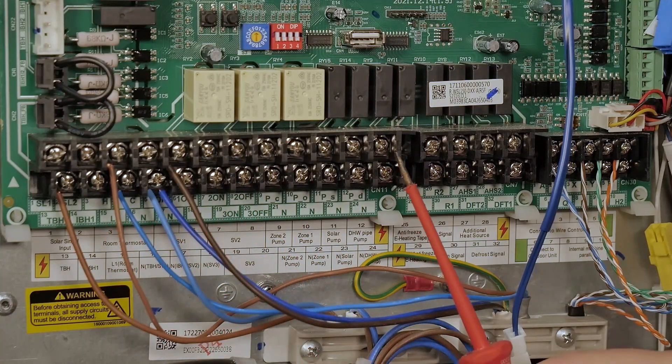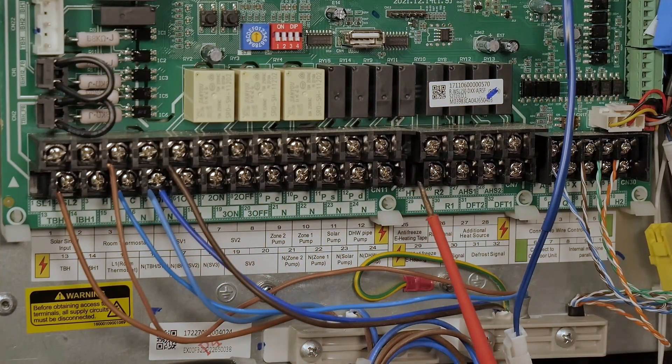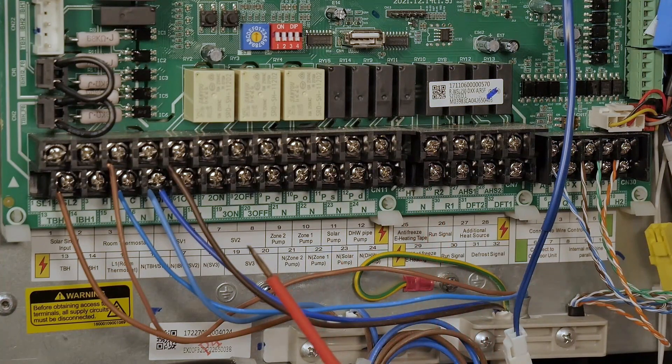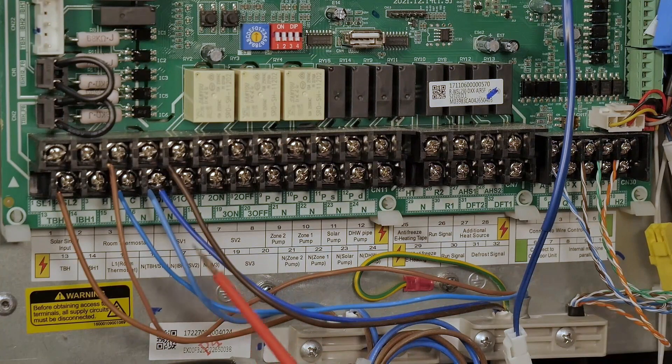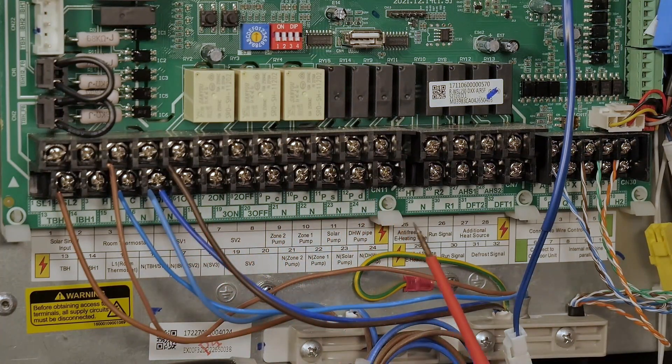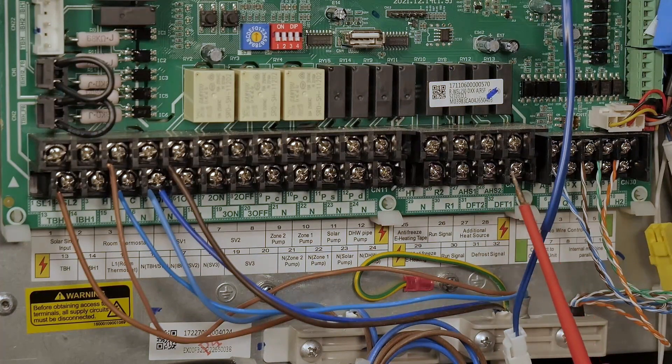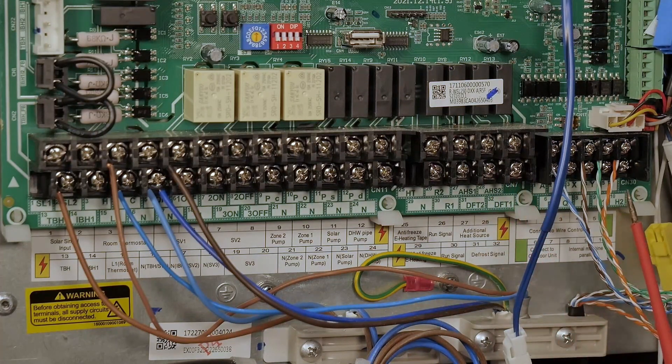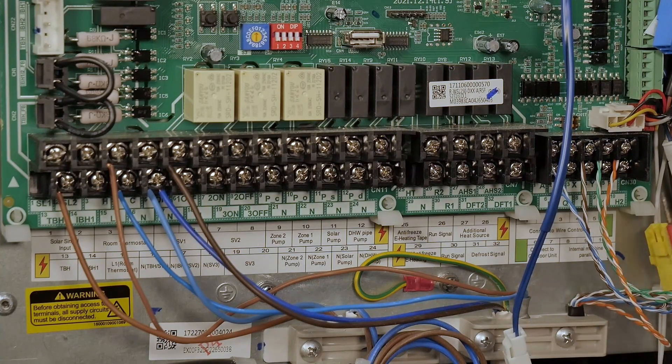This is the initial terminal block CN11, so this is where you'll be bringing in your heating controls, your immersion switching - most of the switching is done through the terminal blocks on this section. This is CN7 which we won't be using at this point, and this is CN30 which is all the terminals for your cat5 cable for your user interface.